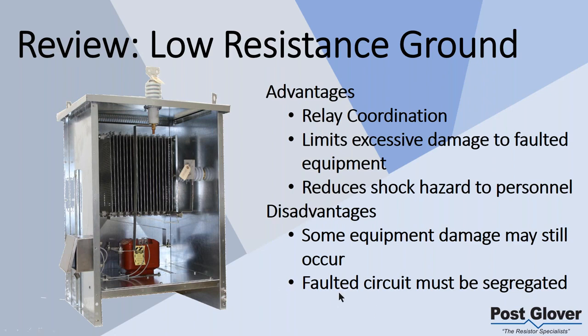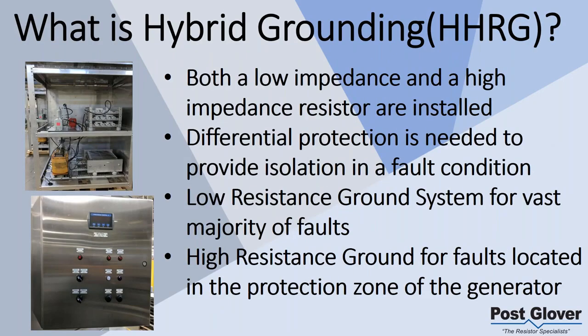Another disadvantage of a lower resistance ground system is you must trip, essentially. It's similar to a solid ground system in that you must trip, whereas with a high resistance ground system you don't have to. Now once again, this is the hybrid grounding system. All it means is a combination of the two, the low resistance ground and the high resistance ground. So that's why I want to go over these two, which is what I just mentioned here.